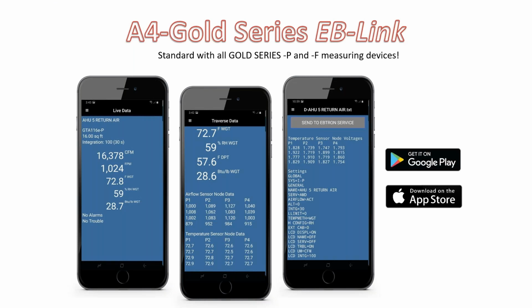It has about a 20-foot radius. Basically what you do is you download a Bluetooth app from your Apple or your Google Play Store. It's called the EBTRON EBLink. It's a free app. And for all of our Gold Series products, you can see what's going on at that transmitter. You can do a traverse, because what we do at EBTRON is we measure airflow at each individual sensor node. We're going to get into that in a little bit. You can do a traverse, and you can also do a diagnostic screen if you ever have any issues with the flow meter. You think it's the flow meter that's having an issue. Before getting on a ladder, you can connect to this with Bluetooth, download the diagnostics data, and shoot this over to our service department who can help you out.